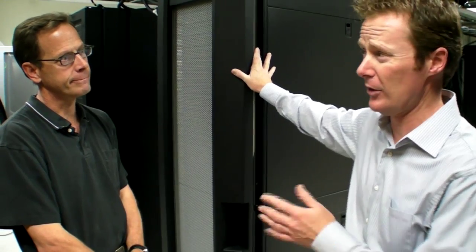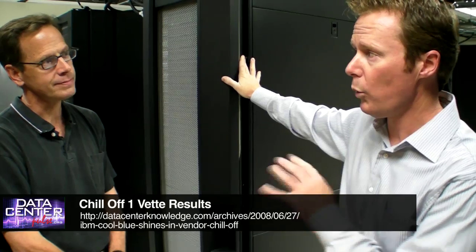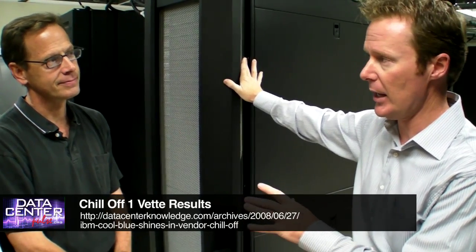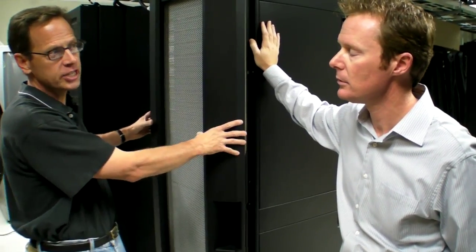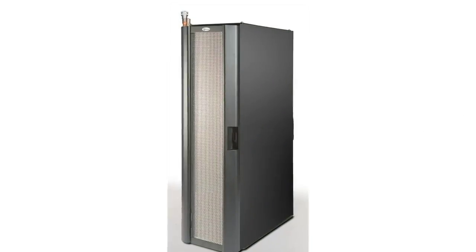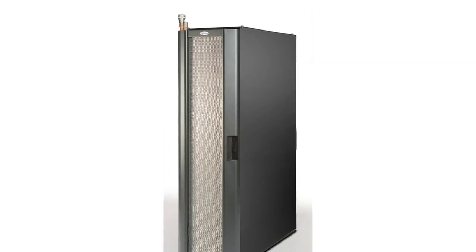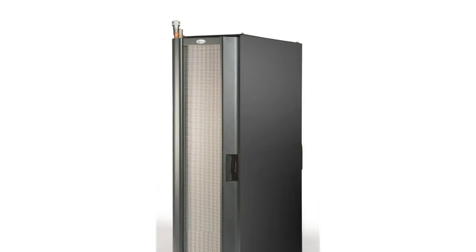And once they do that, the technology has the ability to take out 18 kilowatts worth of load. We actually tested a Vette Corp solution, very similar to a rear door heat exchanger, in the first Chill-Off. This is slightly different from the standpoint of a rear door heat exchanger — it's a very slightly longer length to be able to handle some of the taller racks and slightly more heat loads.